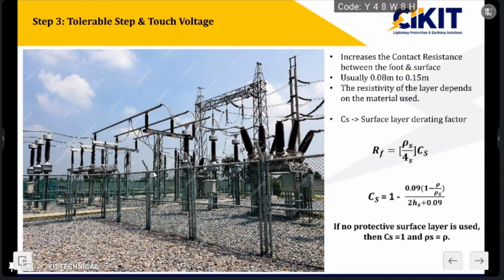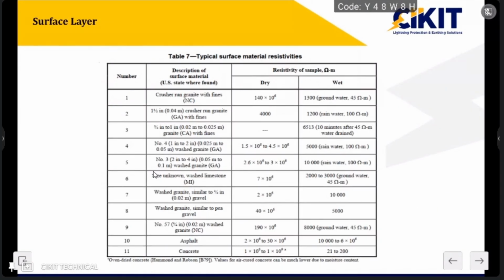The standard has also provided a table which lists the resistivity of different materials commonly used for this surface layer. Normally we go for gravel material. If we go for gravel, the resistivity value will be around 2 into 10 to the power 6 ohm meter. In extreme conditions, if we are performing this calculation and are unable to meet the criteria, then instead of gravel we can go for asphalt, which has much higher resistivity values.